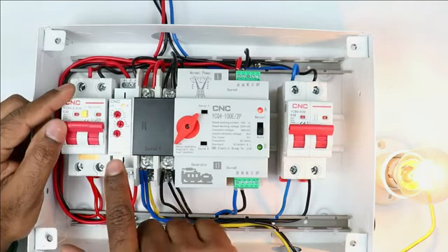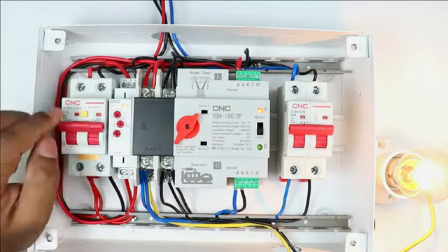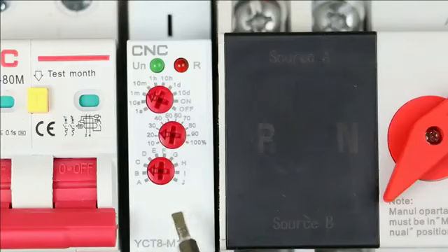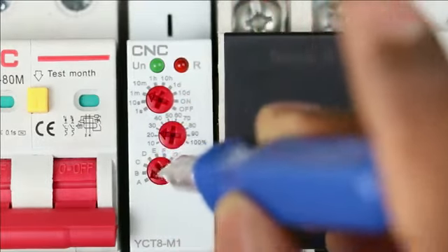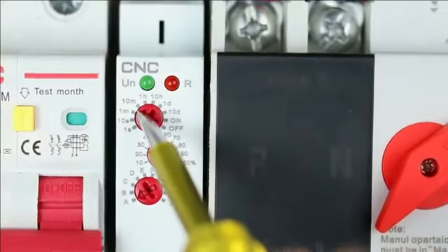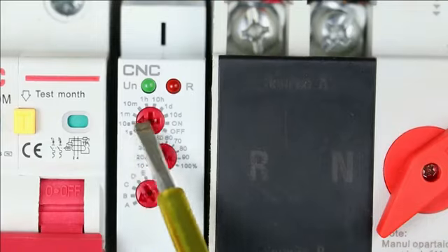I told you before, by using a timer, we can delay this. We have to first select the delay time. I am switching off both the MCBs. I am using this as an on delay timer, so I am setting this knob to A position. A means on delay timer. These two knobs are used for setting time. For now, I am setting this as 10 seconds. I selected the 10-second position.